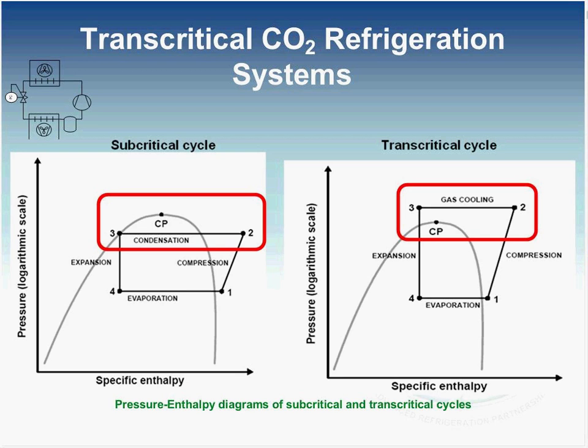Again, we're above the critical point for carbon dioxide, so in that transcritical mode, we don't condense the gas by means of using the ambient air. We just cool the gas and lower the temperature before we feed it to an expansion device that's out in the case. So from a very high-level viewpoint, those are the big differences between the two systems. And accordingly, the higher you are above that critical point, the higher the pressure will be, and that's why we see pressures around 1,600 pounds. As you go below that critical point, you see pressures around the 400 or 300 pound range that you see on the subcritical systems used in supermarkets today.